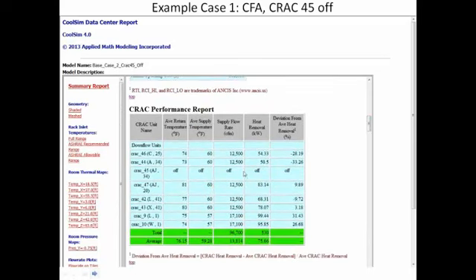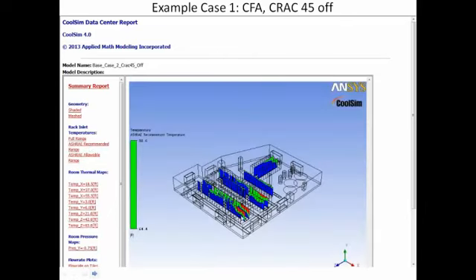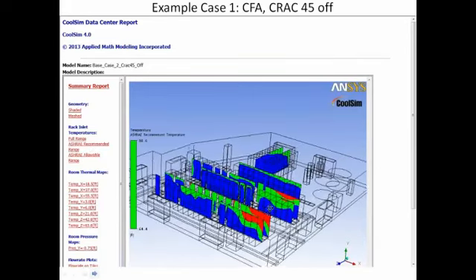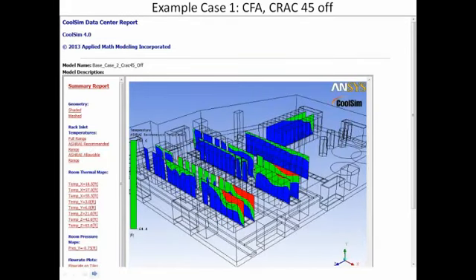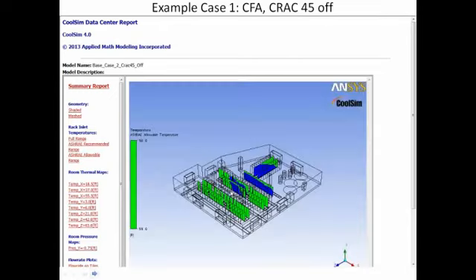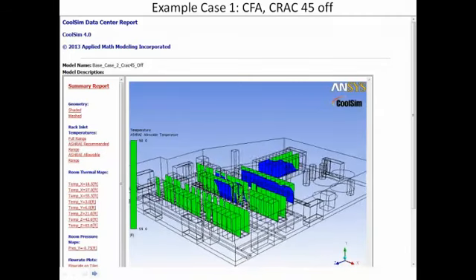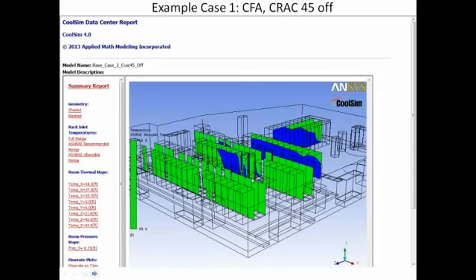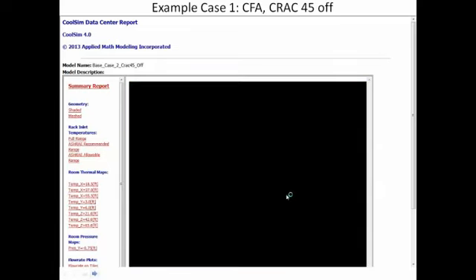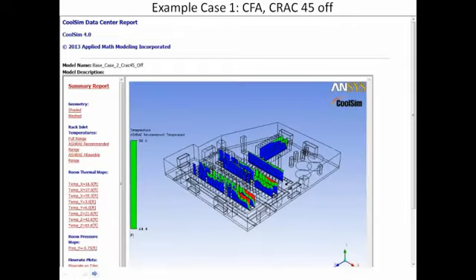And you see here that one of the CRACs is turned off. And if we go back now and look at the recommended ASHRAE range, we see we're in trouble right away. Now, you may say, well, yeah, we're in trouble, but we could probably sustain that for a period of time. And I think that's true. If we look at allowable, you could sustain it for a period of time, and so you may say this is okay. But more than that, I think what we're trying to point out here is that it's important to understand these failure modes so that if a situation occurs where the racks get in trouble, because remember, I'm assuming a particular load here on these racks, and that load may change over time.